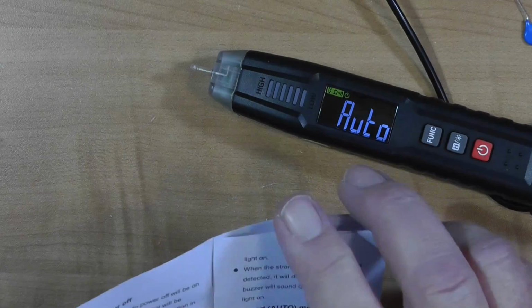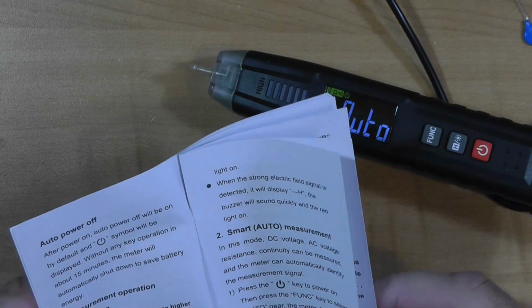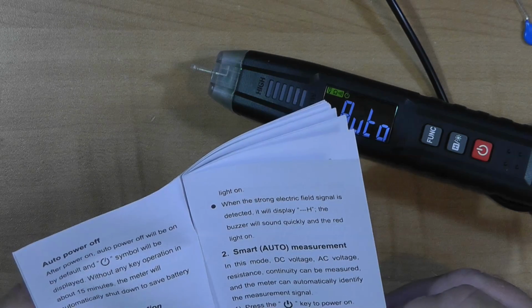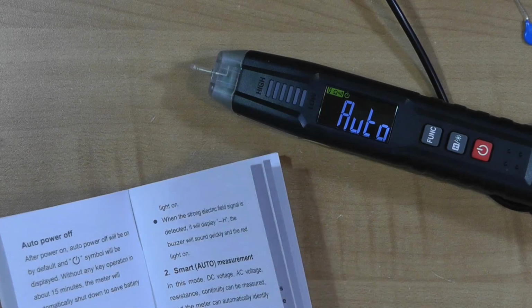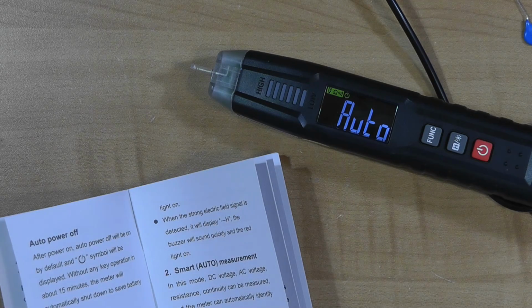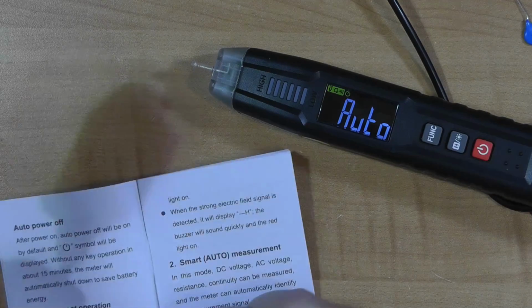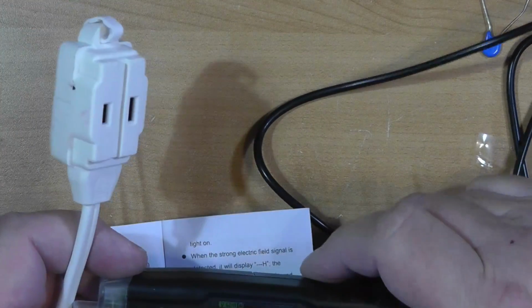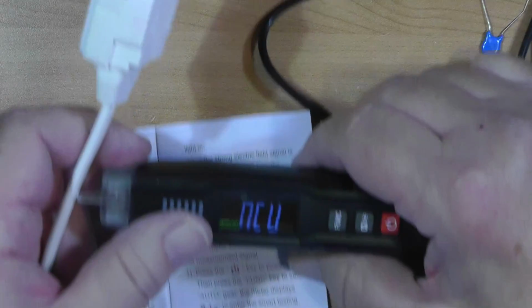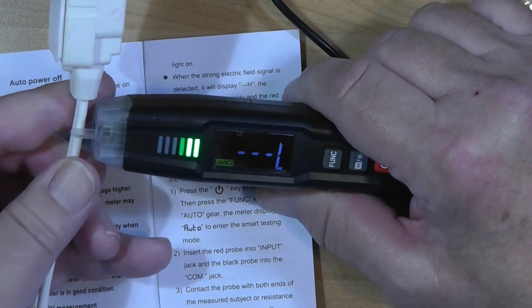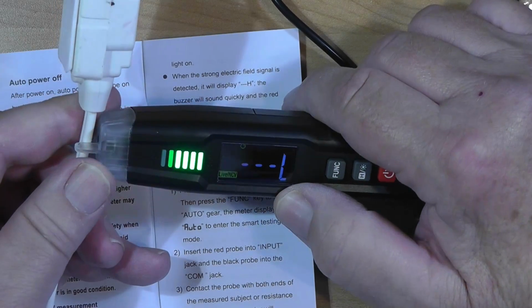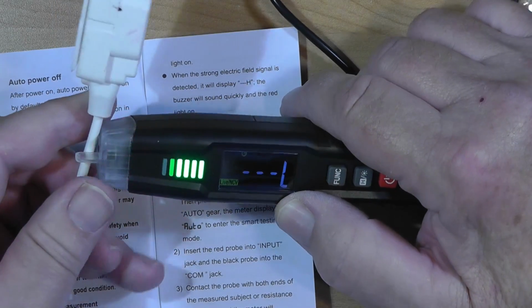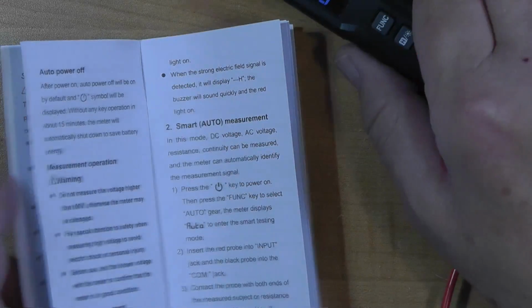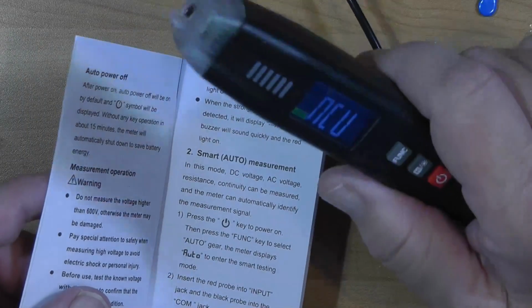NCV measurement, that's the non-contact voltage, and it gives just a strength in lights. When an electric field signal is detected, it will display high. So if we hold the function down, we get NCU, and the H means there is a voltage detected. If it's a high voltage, it's an H. I don't know where it divides the line at high and low voltage. This could be very handy, double checking something before touching anything.